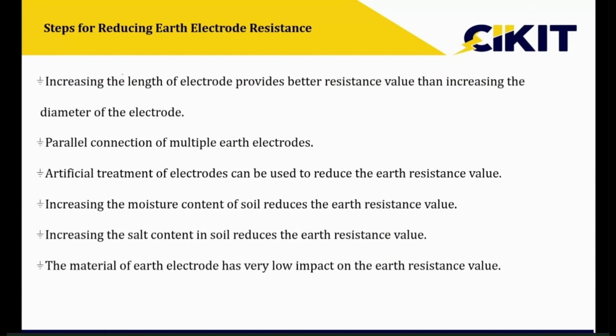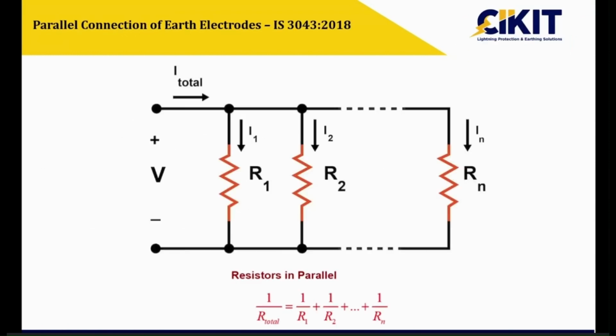So if I'm getting a higher resistance value, then how can we reduce this value? The standard has provided different options, like increasing the diameter or increasing the length, then increasing the number of electrodes or providing this enhancing compound. So we can use any of these processes for reducing the earth resistance values.